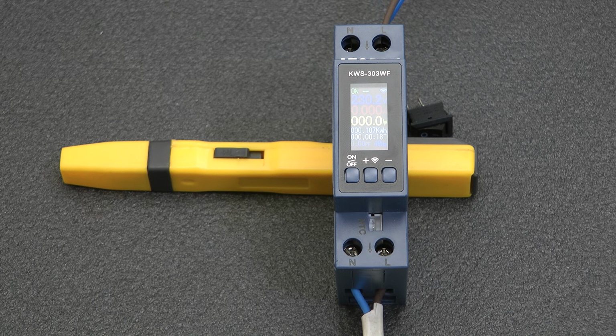Where can it be installed? For example, on a boiler, pump, underfloor heating, charger, lighting, or any load where you want to see consumption and have remote control. But I would not constantly run it at the 40 amp limit, especially without a proper electrical panel, good terminals, and a power reserve.